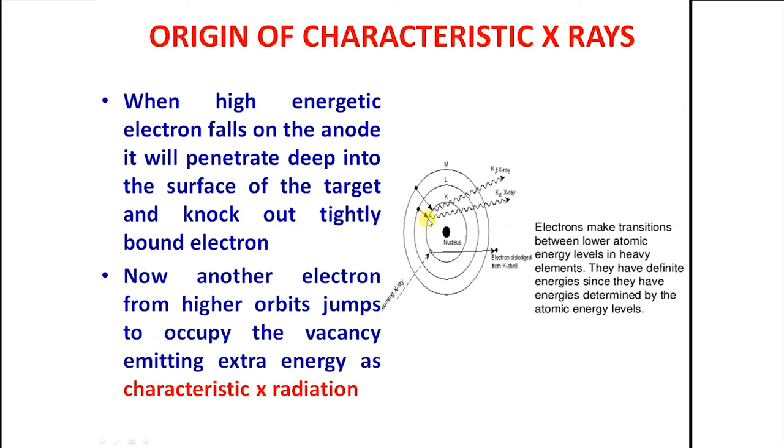When the electron is accelerated, when it goes deep into the atom, which can dislocate one of the electron in the K shell, but this vacancy may be filled up by higher energy electrons. So when this vacancy in the K shell is filled up by higher energy electrons, these electrons jump into the lower level resulting into additional radiations. These radiations are called characteristic radiations or characteristic x-rays.